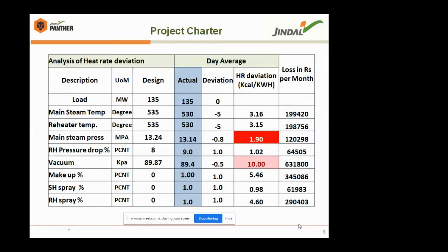We have observed how the deviation of parameters impacts the heat rate, as given in the table. For example, suppose our unit is running at 135 megawatt and our design temperature is 535, and we are maintaining the main steam temperature at 530, that is -5 degrees from the design value. Then there is a heat deviation of around 3 kilocalorie per kilowatt hour. That means for 1 unit there is a deviation of 3 kilocalorie in turbine heat rate, which, in terms of money, is a loss of 2 lakhs a month. This is calculated by considering the coal cost as 0.65 rupees per megacal.